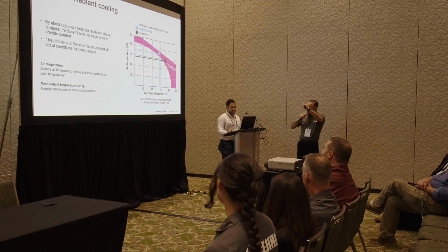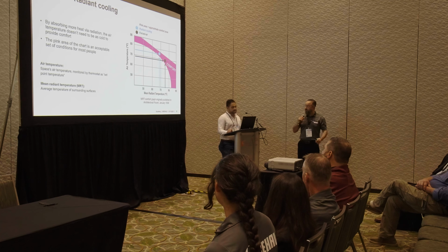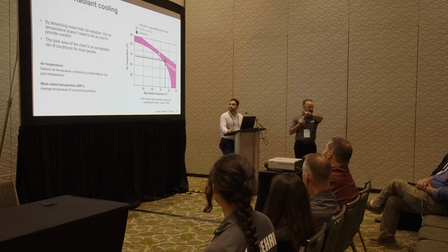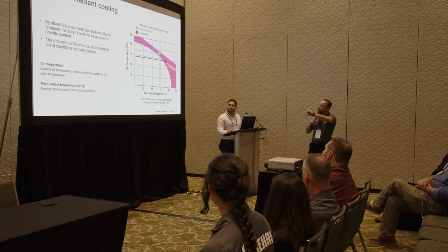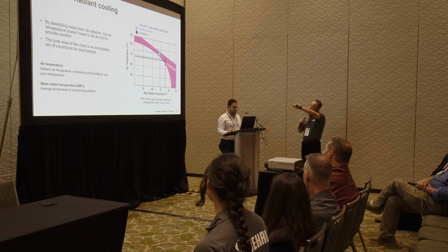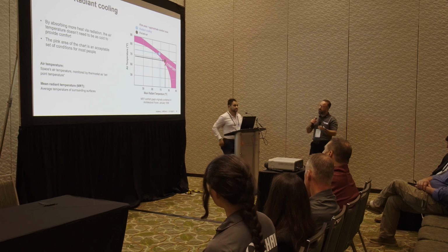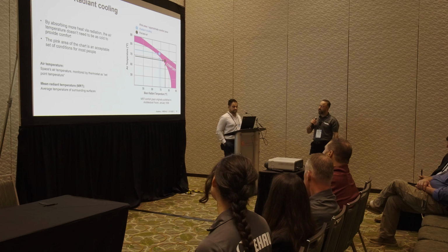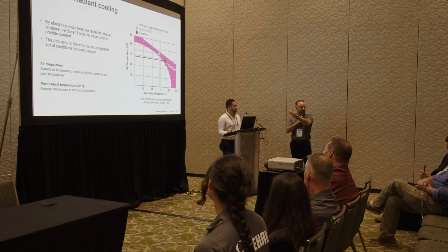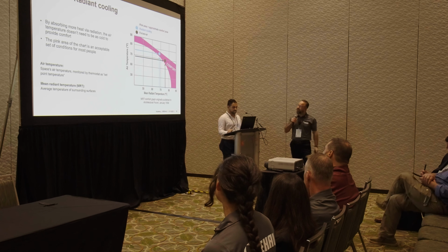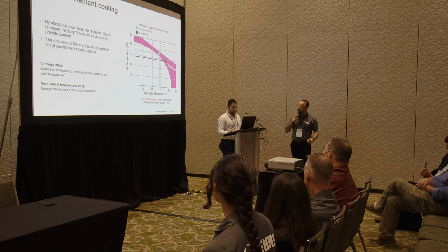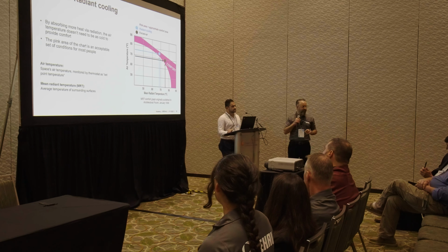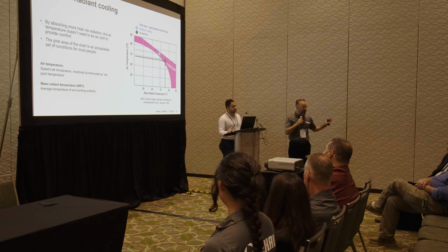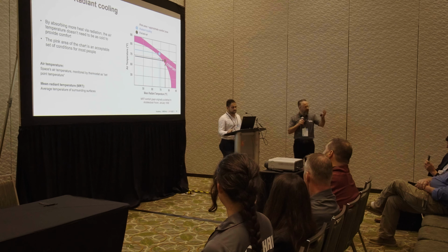This graph was actually published in 1939. That pink area represents where your body functions in a comfortable range. And you can see that the blue dot is representing the radiant cooling application versus a forced air, which is represented by a black dot. You can see when we are taking advantage of mean radiant temperature, the surrounding temperature, we can let the air temperature inside the room be a little bit higher than normal.